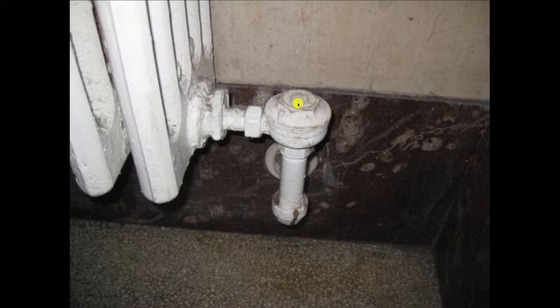And the way it works is inside the cover here, we've got a bellows that's partially filled with a volatile liquid. Typically, it's alcohol. And we pick a liquid that boils at a temperature lower than water. So alcohol will boil at about 180 degrees. And we put this in here, and the bellows is partially filled with the alcohol, brought up to temperature, and then sealed while the alcohol is boiling. And then they remove the heat and allow the bellows to cool.